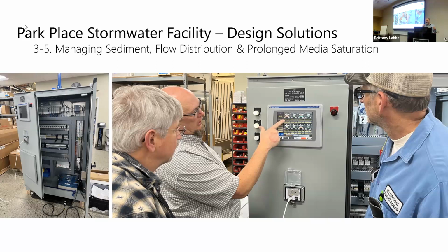We have a couple other really fun things. Once you can control systems in this way, it turns out you can run other experiments. One of the other questions in the industry is, how much do the plants do? Because the post media can be in a planted configuration and an unplanted one. So we were able to build into the PLC a designation: we planted two cells and left the other ones unplanted. There's a mode of operation where we can run it planted only or unplanted only, and we're set up to do monitoring, and so we can compare the effects of that.